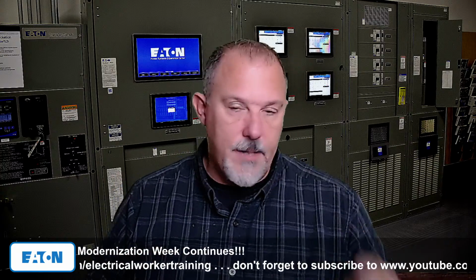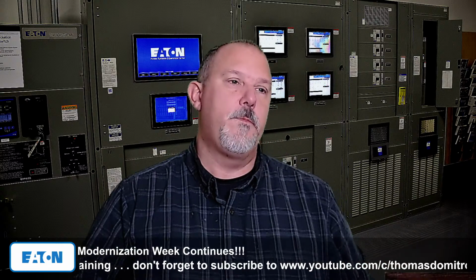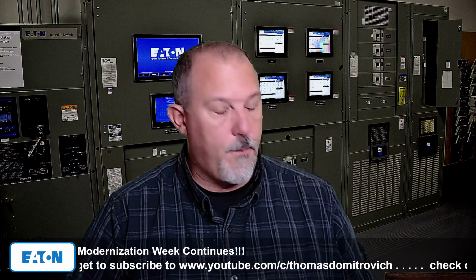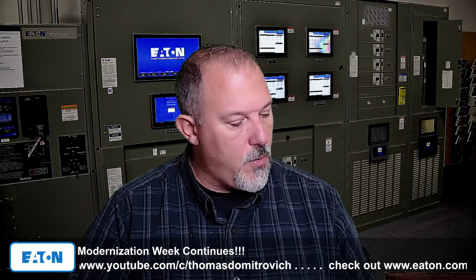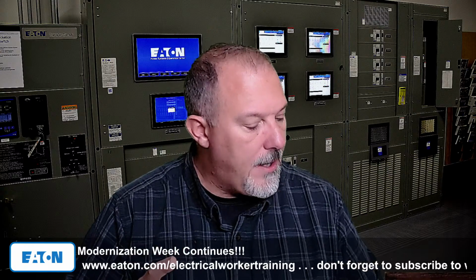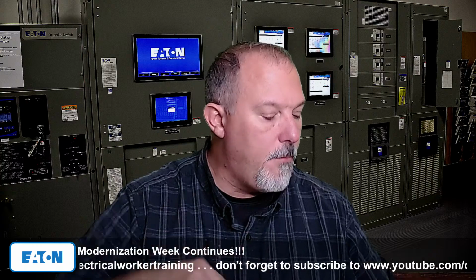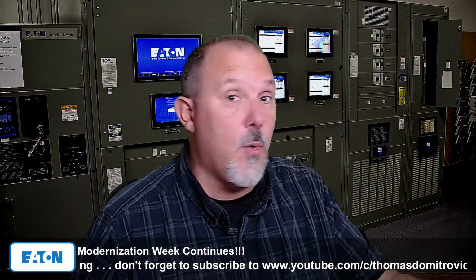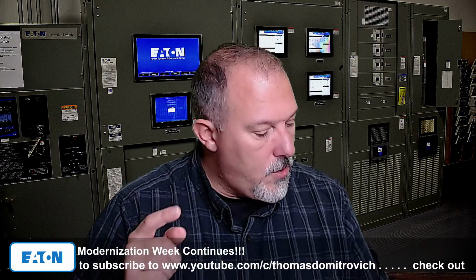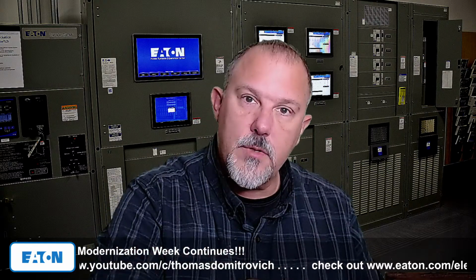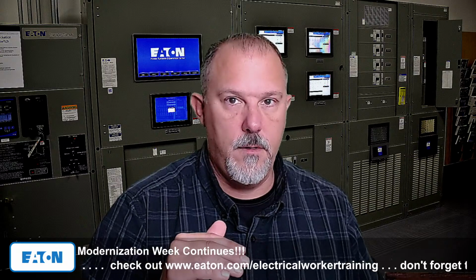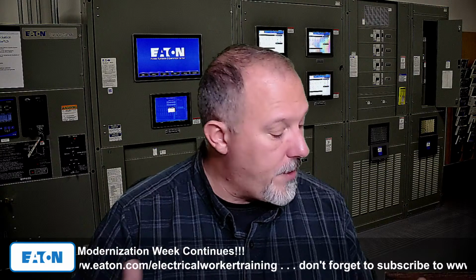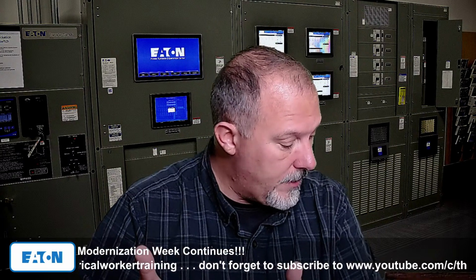210.52, dwelling unit receptacle outlets. And in the parent text of 210.52, it says, this section provides requirements for 125 volt, 15 and 20 amp receptacle outlets. The receptacles required by this section shall be in addition to any receptacle that is as follows. And if you look at item 4 on that list, it says located more than 5.5 feet above the floor. So what I would say is the receptacle outlet requirements in 210.52, that height is going to be 5.5 feet. So I can put it 2 feet off the floor. I can put it 3 feet off the floor. There is no minimum. I can put it in the floor if I wanted to, right? I can put it anywhere in the wall.